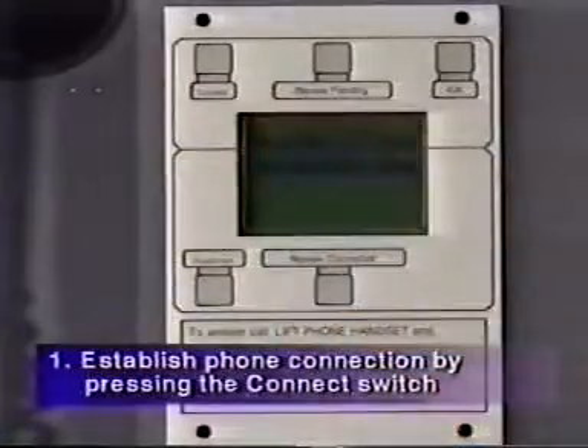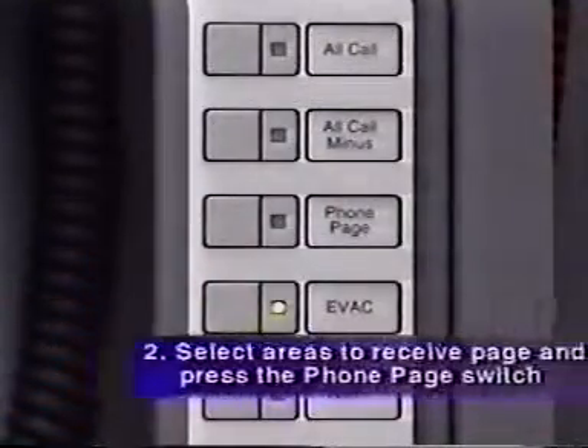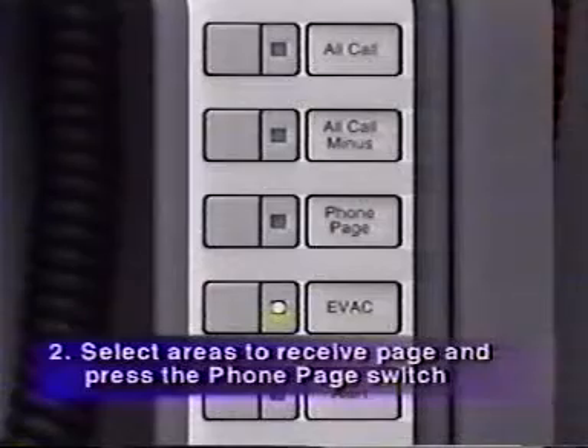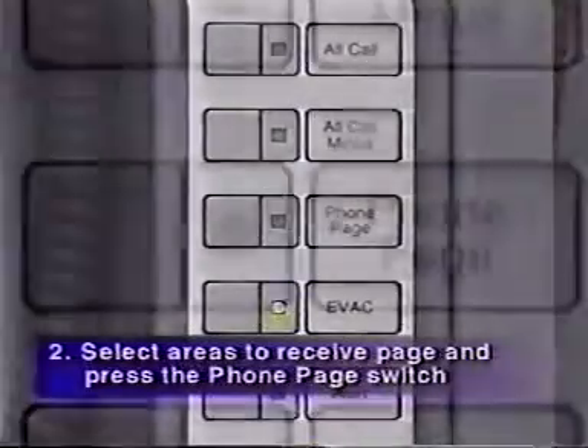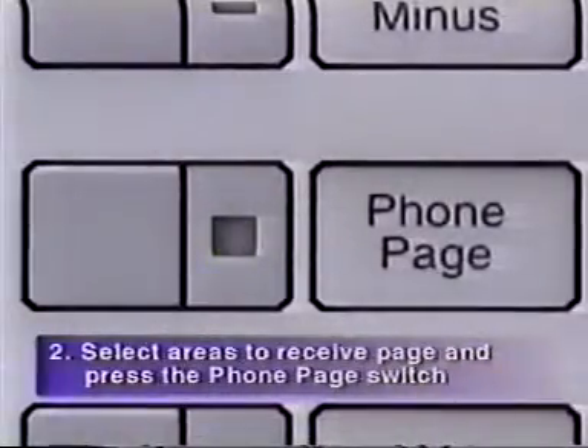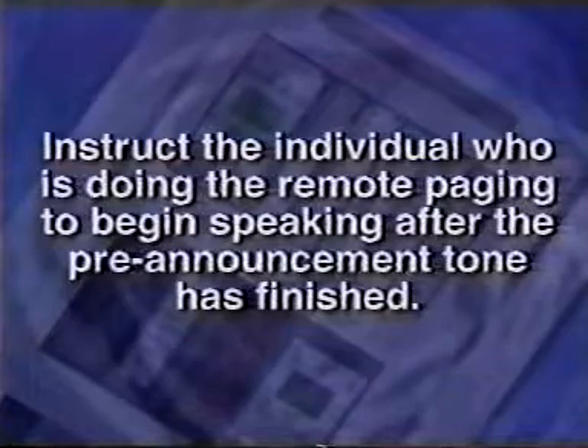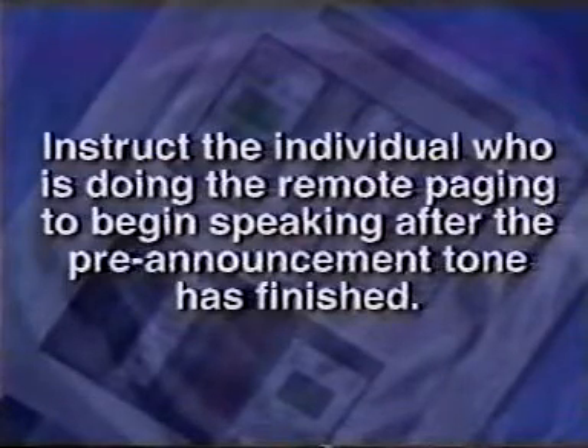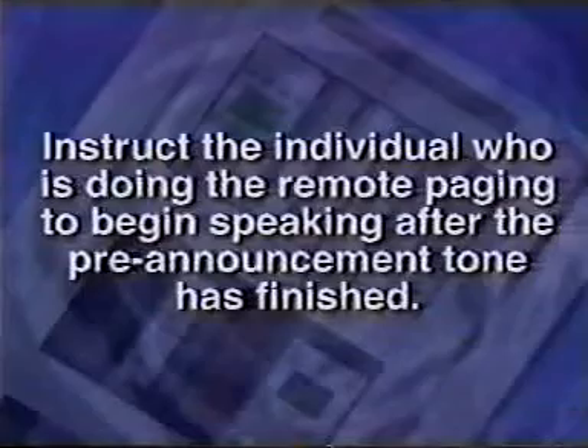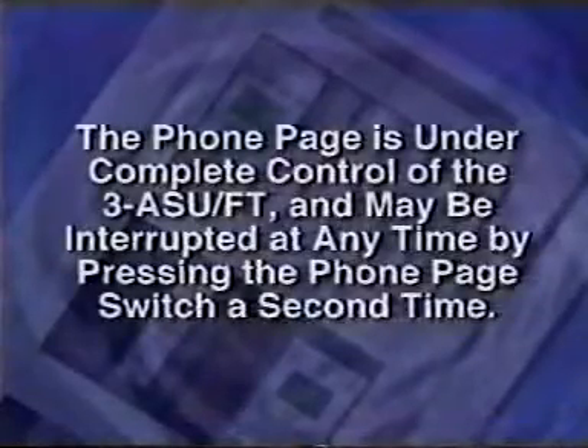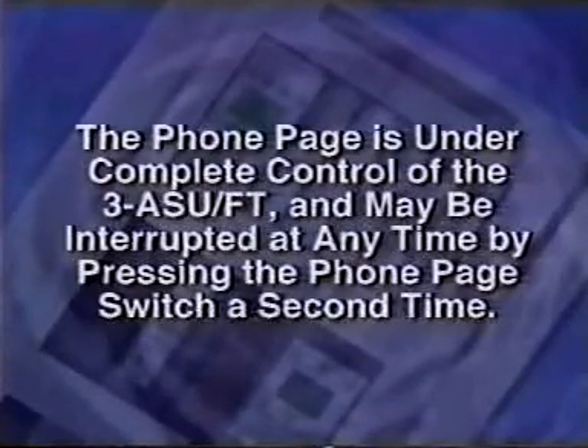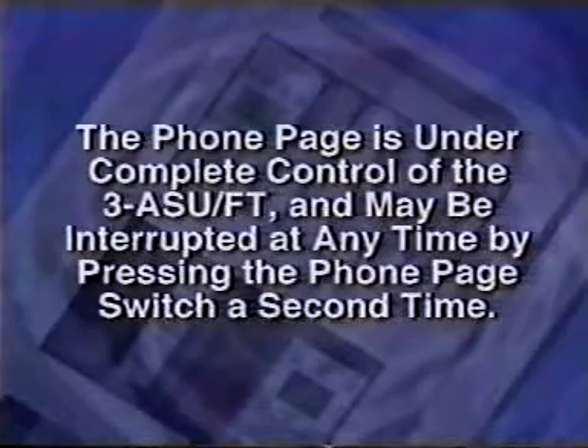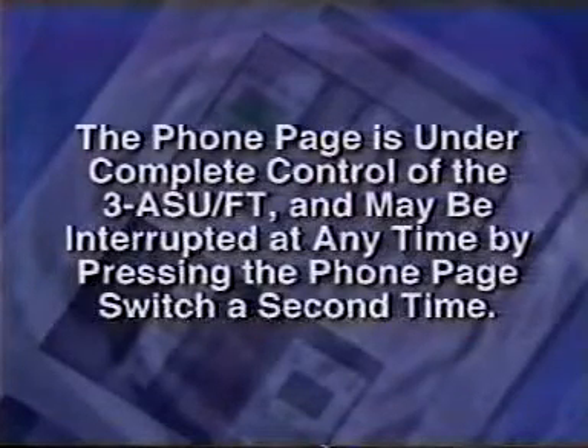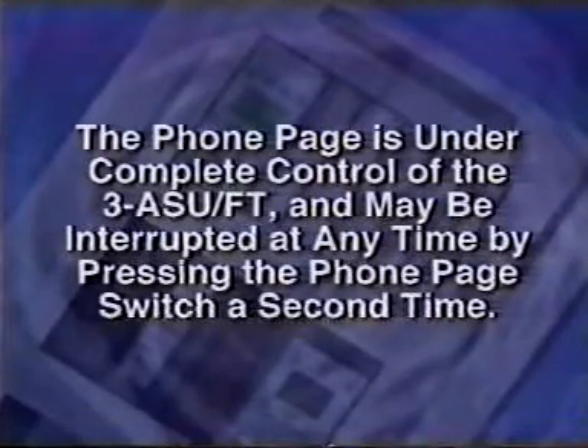the Connect switch. Select the areas to receive the page the same way you would when using the 3 ASU microphone. Then, press the phone page switch and instruct the individual who is doing the remote paging to begin speaking after the pre-announcement tone has finished. Keep in mind that the phone page is under complete control of the 3 ASU FT and may be interrupted at any time by pressing the phone page switch a second time.